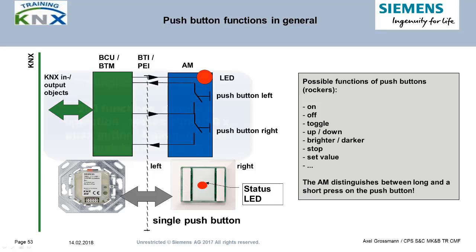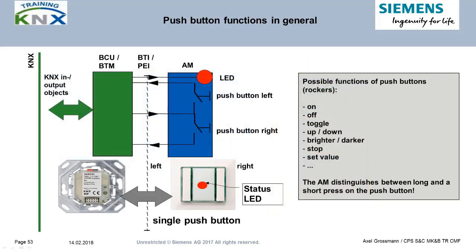KNX push buttons are much more universally usable than their classic siblings, which also means much easier planning. You simply need to summarize all required functions for the room, divide by the number of buttons or rockers of one device, and that gives you the number of devices needed. No distinction for types of switches such as interrupting, changeover, or crossover switch, dimmer, or blind switch is necessary anymore.